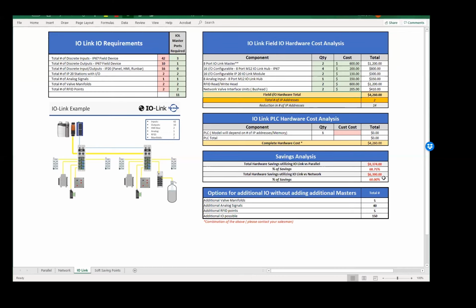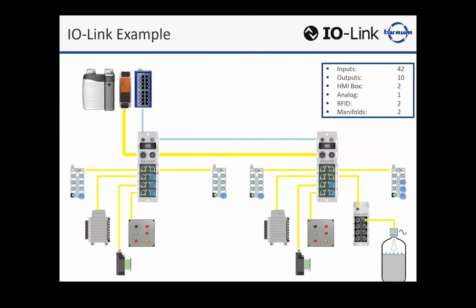Let's talk about first that with IO-Link, you're going to use standard media. So in between your masters, you're still going to use network media, in this case, an Ethernet IP cord. But that's only from the panel to each master. You can see all the devices coming off the master are using standard media. When I say standard media, I mean a regular 4-pin or 5-pin tool cord based on the device you're connecting to. So typically, those are anywhere from 40 to 50% less than the network cable. So we're using readily available prox cords off the shelf to do our communication, and only keeping network media at the upper level of the masters.